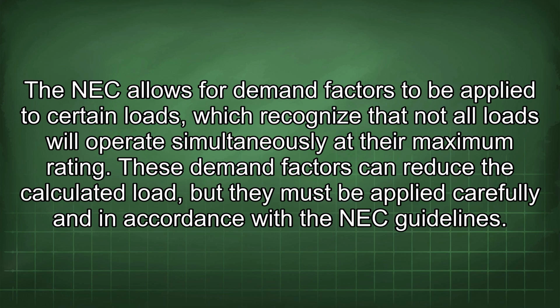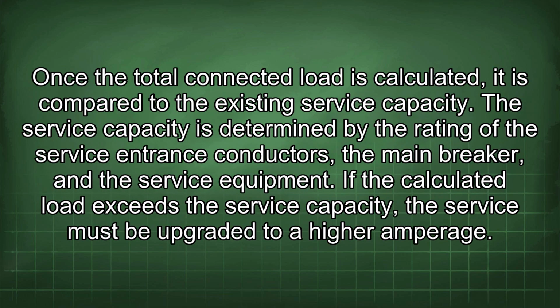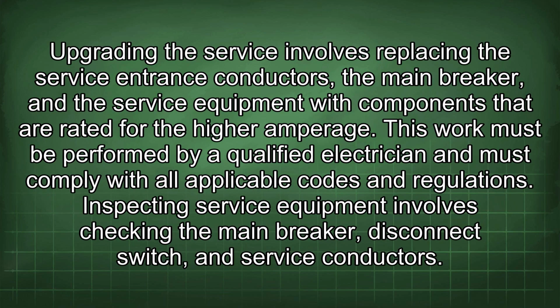These demand factors can reduce the calculated load, but they must be applied carefully and in accordance with the NEC guidelines. Once the total connected load is calculated, it is compared to the existing service capacity. The service capacity is determined by the rating of the service entrance conductors, the main breaker, and the service equipment. If the calculated load exceeds the service capacity, the service must be upgraded to a higher amperage. Upgrading the service involves replacing the service entrance conductors, the main breaker, and the service equipment with components that are rated for the higher amperage. This work must be performed by a qualified electrician and must comply with all applicable codes and regulations.